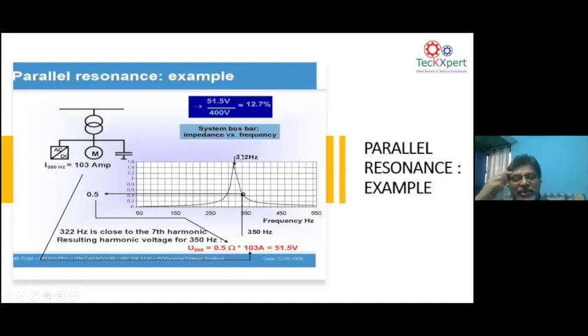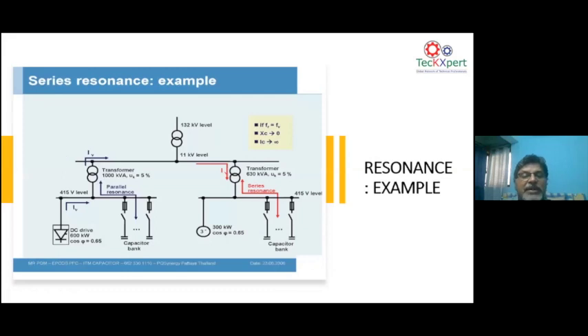So sometimes when you do harmonic measurement, if you see big harmonic voltage distortions or harmonic current distortion, you should doubt the capacitors there must be causing parallel resonance with the impedance of the network because of the variable nonlinear load present in the network. There is also something called series resonance. The resonance can be of two types.